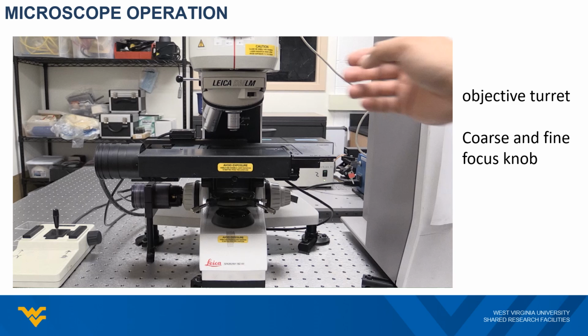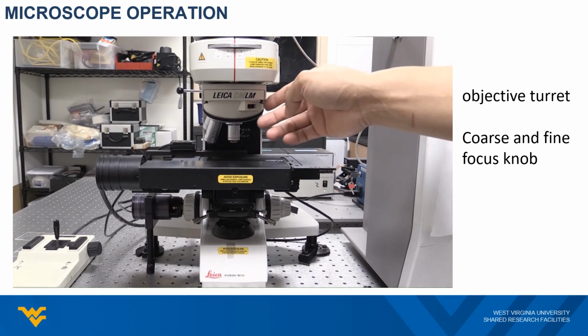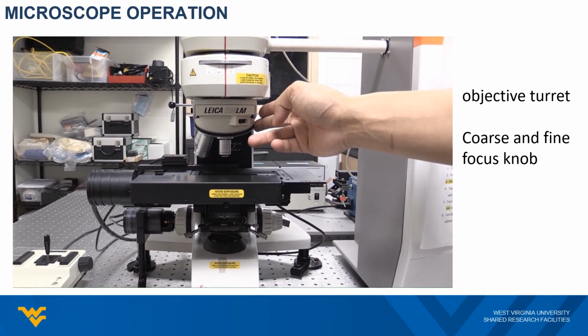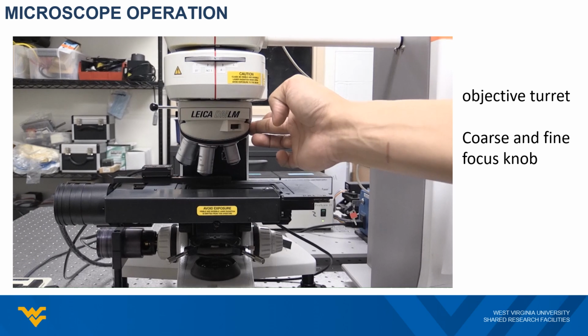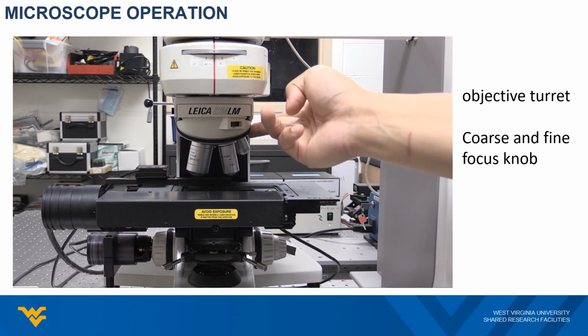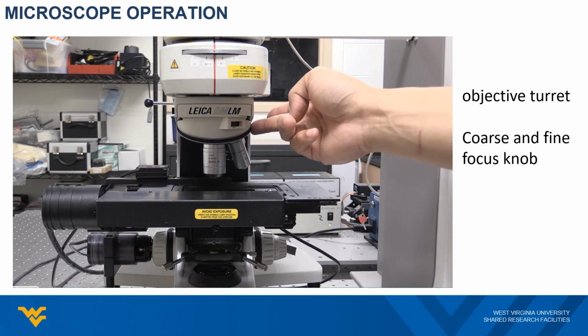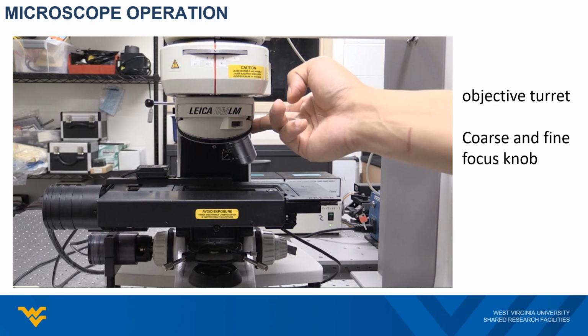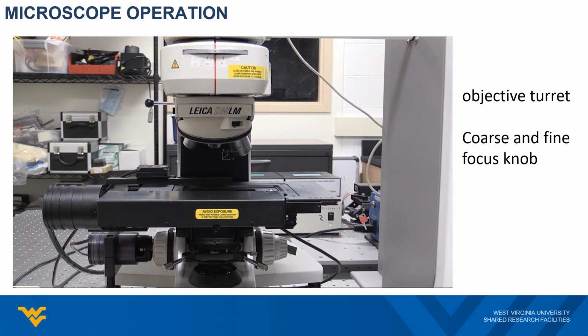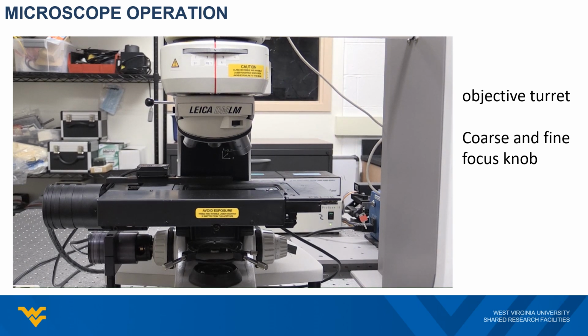Now let's go through some basic microscope operations. Our microscope is equipped with 3 objectives: the 5 times, the 20 times, and the 50 times objectives. All those 3 objectives are mounted on the objective turret and can be switched manually. When loading samples, I suggest rotating all the objectives away to protect optics.